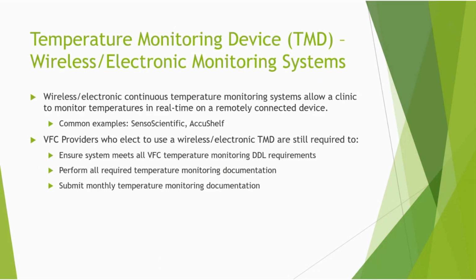Wireless electronic continuous temperature monitoring systems are also an acceptable TMD as long as they meet all the necessary DDL requirements. Wireless or electronic TMD systems allow a clinic to monitor temperatures in real time on a remotely connected device. VFC providers who elect to use a wireless or electronic TMD are still required to ensure the system meets all the VFC temperature monitoring DDL requirements. They must perform all required temperature monitoring documentation and also submit those monthly temperature documents to the DOH email. Next slide, please.